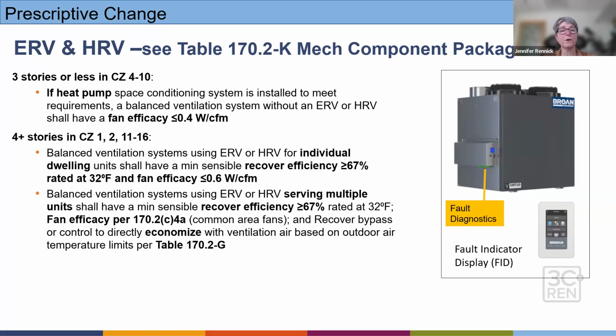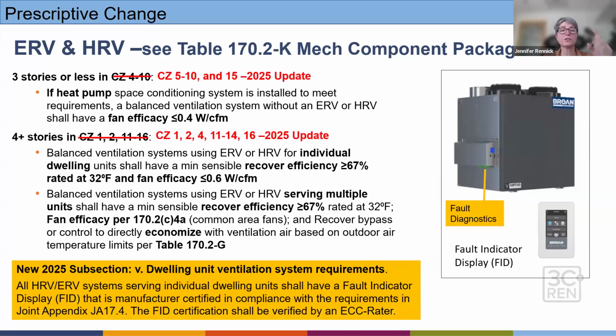yes, it is part of the current code, and there are fan efficacy requirements and recovery efficiency requirements. What is changing is that the climate zones each of these requirements applies to have been updated, and that all the HRV, ERV systems serving those individual dwelling units shall have that fault indicator display that we talked about earlier, and that the FID, or fault indicator display, certification or installation shall be verified by an ECC rater. So there's some increased work for the HERS raters coming up in the code, but not much.